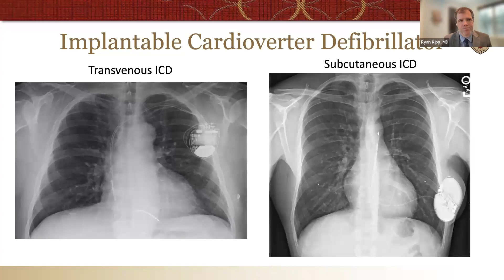And if it determines that ventricular tachycardia is occurring, it'll deliver a defibrillation or a shock, again from the coil to the can and back again, to hopefully terminate the arrhythmia. In contrast to transvenous ICDs, subcutaneous ICDs cannot deliver that rapid pacing to terminate the rhythm without a shock. Additionally, the device cannot deliver pacing if the patient develops bradycardia.